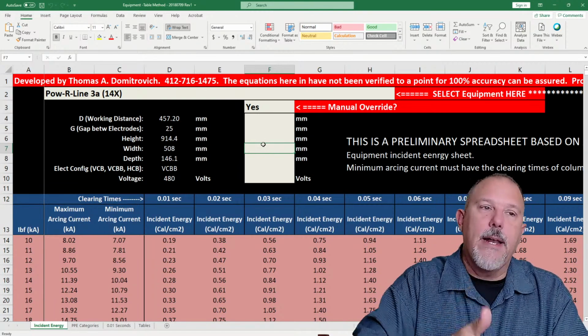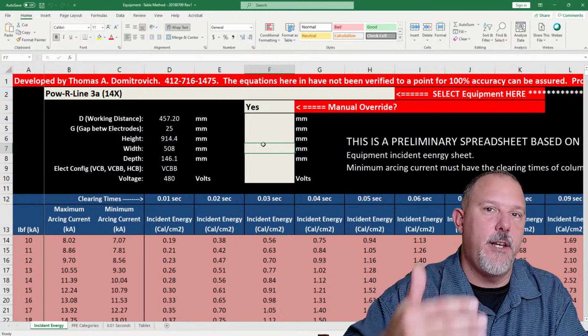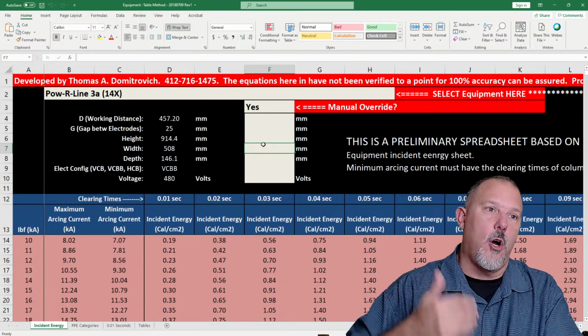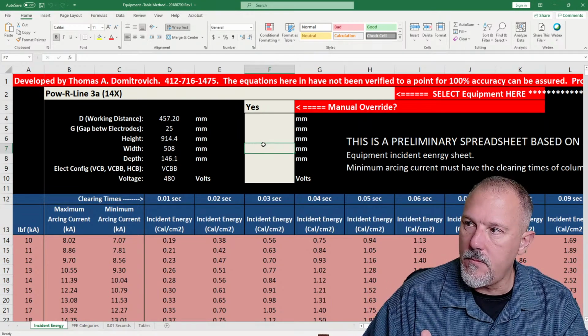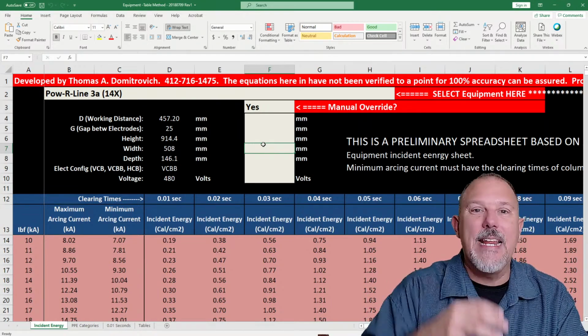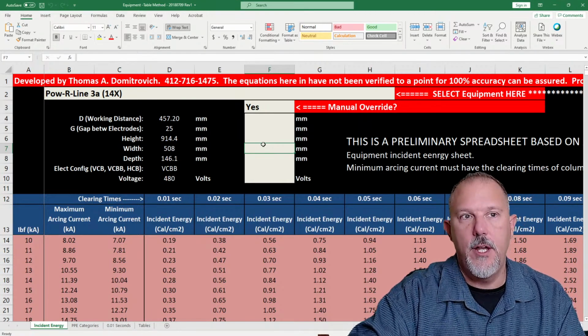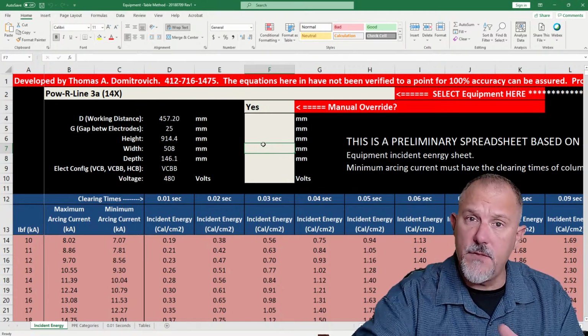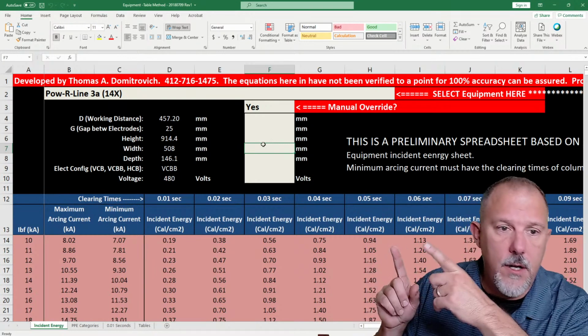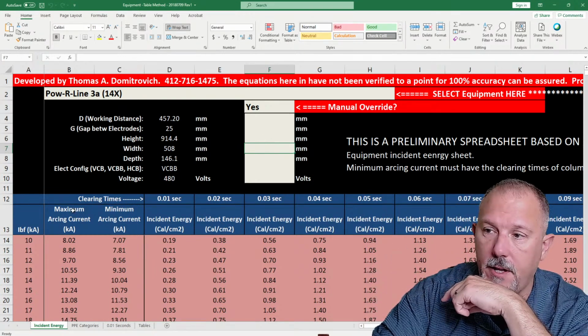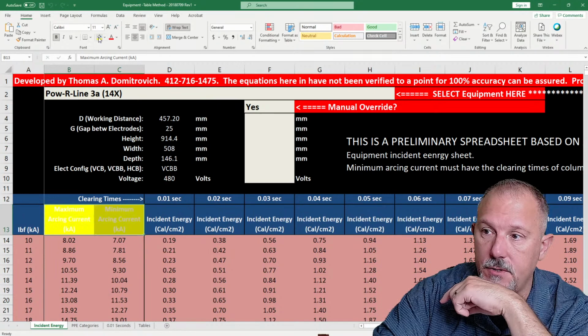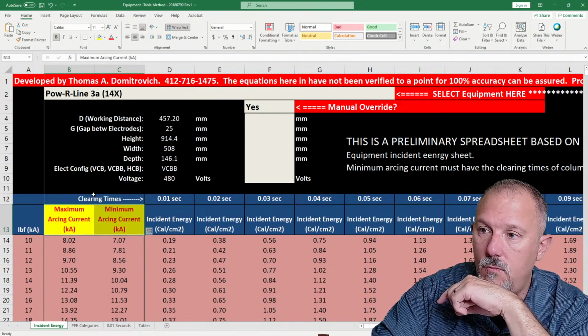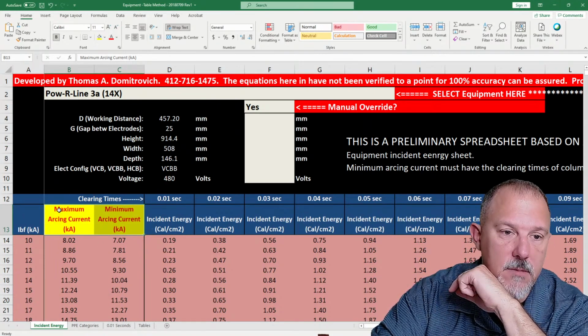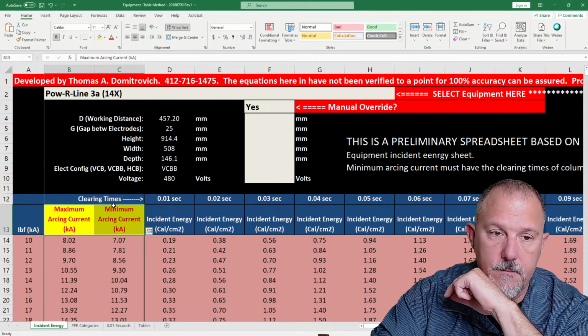Before we even try to come up and make something generic for arcing current, you have to understand what the parameters of a piece of equipment are that impact the maximum and minimum arcing currents, right here, these two values. What impacts maximum arcing current and minimum arcing current?